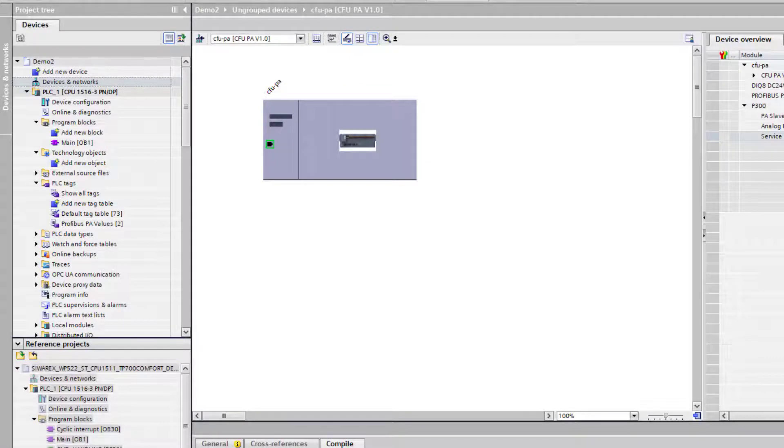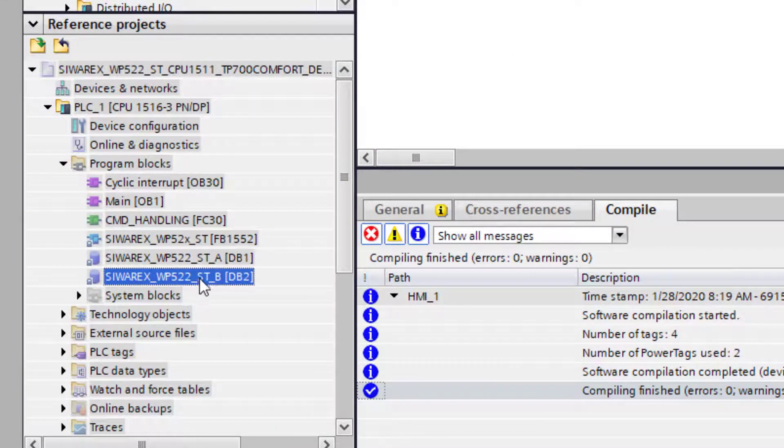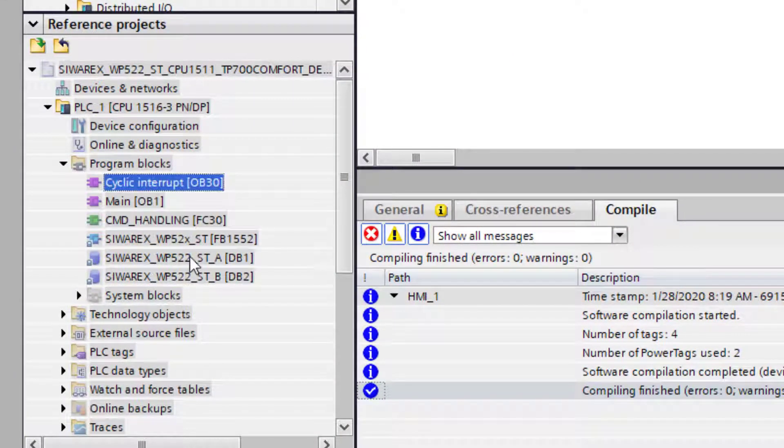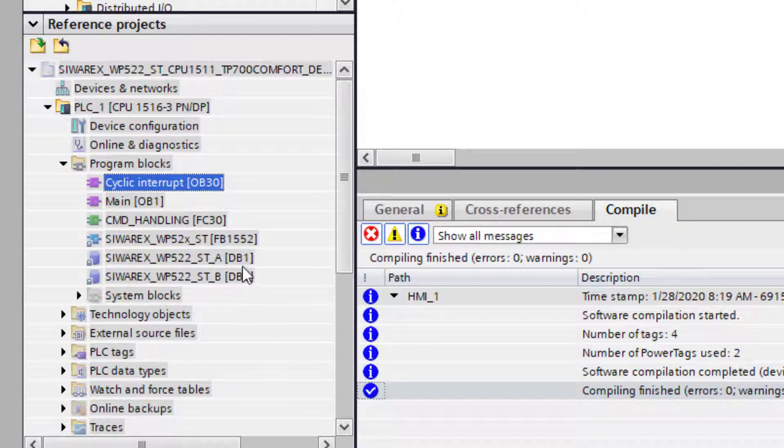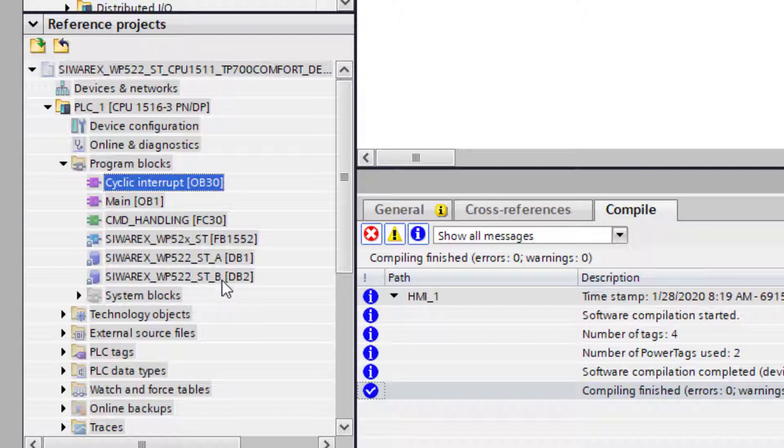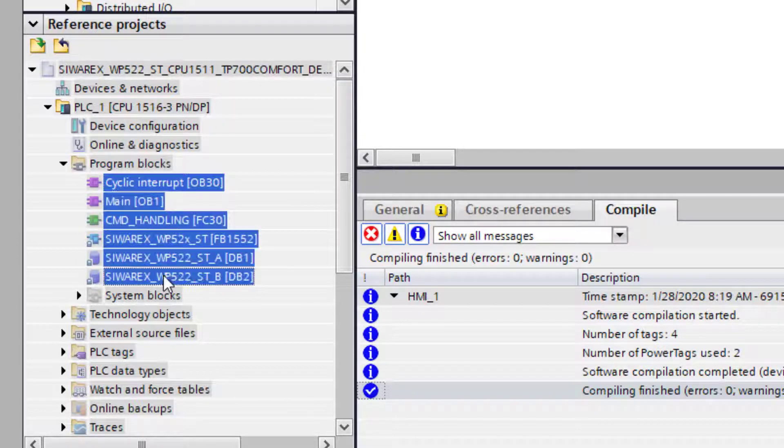If you have a look at the blocks there are two data blocks, and my advice really is to copy all of these including the data blocks. We can change the data block number if it conflicts with something in your project, but TIA Portal has a symbolic link here to the HMI, and if you keep it exactly as it is in this project, when you come to the HMI later on it means there's less work to do.